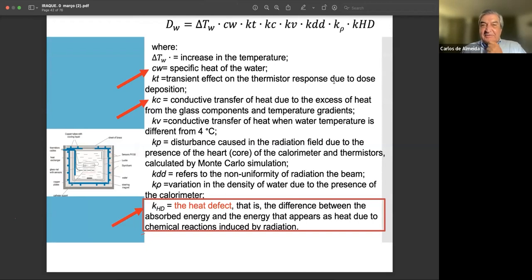See here, just to have an idea of the complexity, you have the specific heat of the water factor. You have the transient effect of the thermistor response due to the dose deposition, conductive heat transfer due to the excess of heat from the glass components where you have the sensors. And then the most important one is the heat defect. That is the difference between the absorbed dose, the absorbed energy, and the energy that appears as heat due to chemical reactions induced by radiation. You have the heat defect for all the materials, not only for graphite, but also for water.